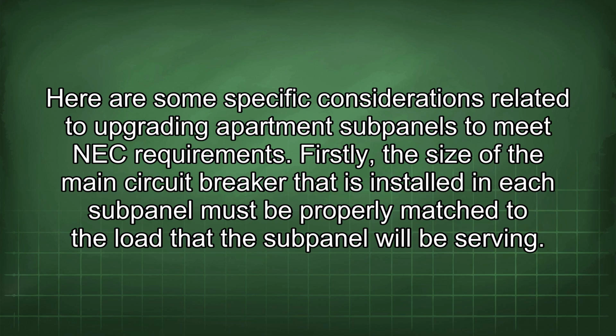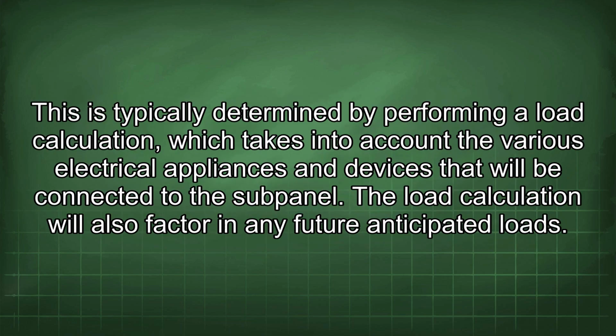Firstly, the size of the main circuit breaker that is installed in each subpanel must be properly matched to the load that the subpanel will be serving. This is typically determined by performing a load calculation, which takes into account the various electrical appliances and devices that will be connected to the subpanel. The load calculation will also factor in any future anticipated loads.